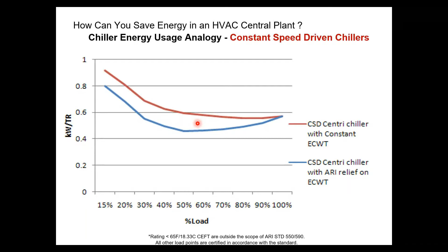Okay, so I'll just try and explain this. This is something which will probably give some idea. If you see the one on the top, I'll just enable the light. This graph is the constant entering condenser water temperature graph. That means from 100, 90, 80, 70, 60, part load is happening, but there's hardly any relief on the condenser water. So this is a constant condenser profile. This is the centrifugal chiller with ARI relief. There is an ARI relief happening over here, and it is sliding. This is the profile of the power consumption when there's an ARI relief happening. There is a marginal gap between these two. Of course, you'll have improved efficiency with the ARI relief on the condenser.